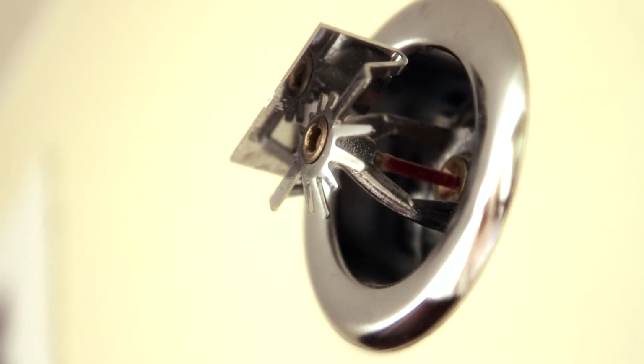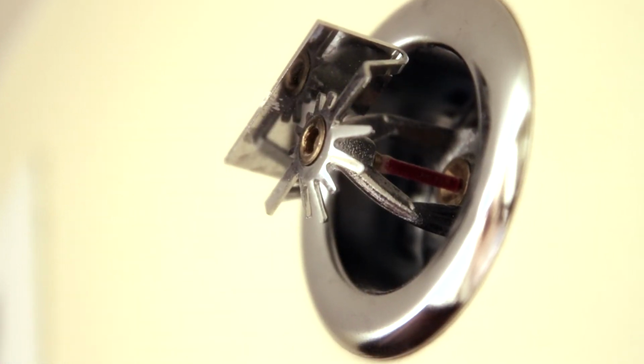Everybody's always afraid that if they put sprinklers in their building, they're going to flood out their stuff, whether it's archives and records or art museums and so forth. But they're never going to do that. This has been tested time and time again. They either have a fusible link or a frangible bulb, and it breaks at a certain temperature rating, and then that's when the water flows out of that head. All the other heads around it are going to be fine until the heat triggers their actuating mechanisms.